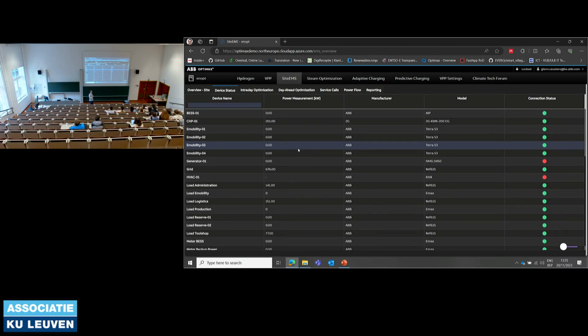And with real trouble, I mean there is, of course, always a grid limit, so there's only so much you can buy or exchange from the grid. Especially now in the Netherlands, with all the net congestion problems they currently are facing, it's really a big problem where you really have to have this real-time optimization loop, because otherwise, if you don't do anything for 5 minutes, the fuse will definitely blow, let's say. The real electrical engineers here might know this is maybe not true, because it's not overload protection, a breaker typically, it's short circuit protection. But still, it's not a good idea to exceed the grid limit for any period of time. And that's why you really have this real-time optimization loop in place.